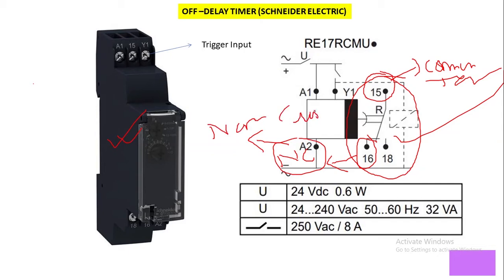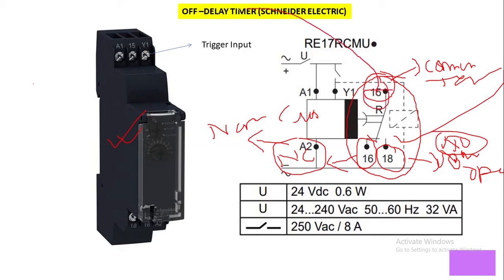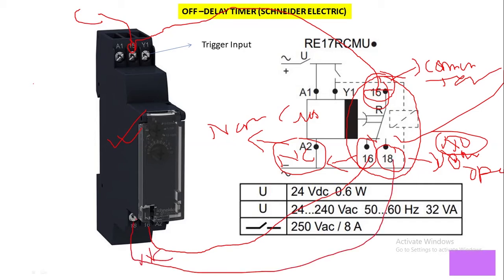Terminal 16 is the NC contact — normally closed contact — and terminal 18 is the NO contact — normally open contact. Looking at the timer physically: 15 is the common terminal, 16 is the NC terminal, and 18 is the NO terminal.